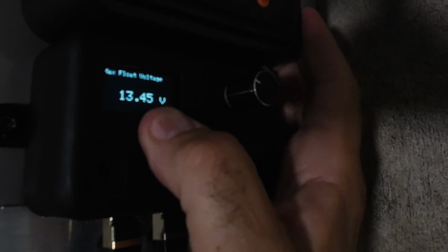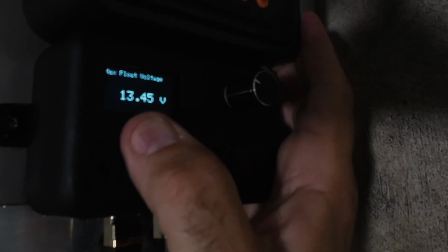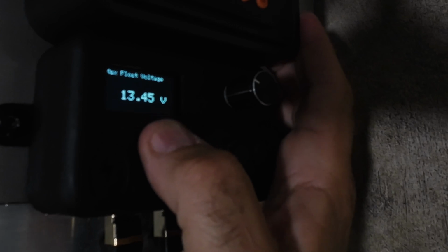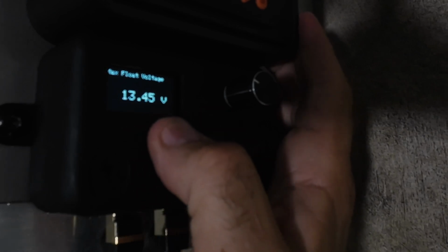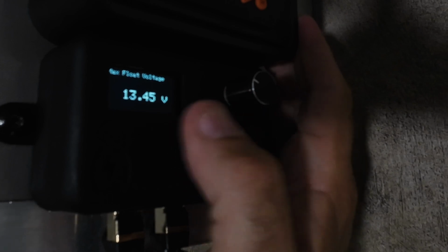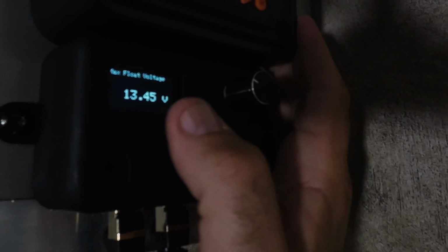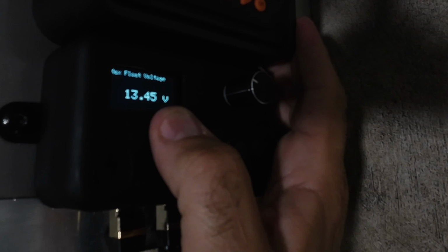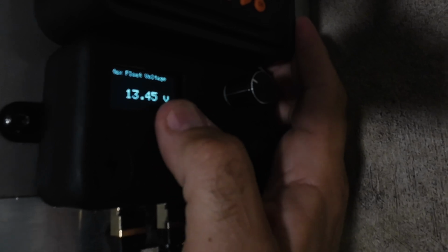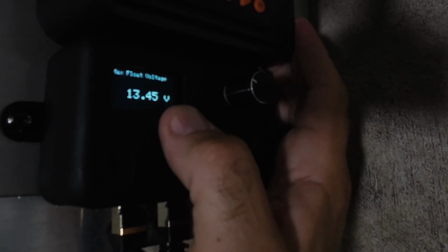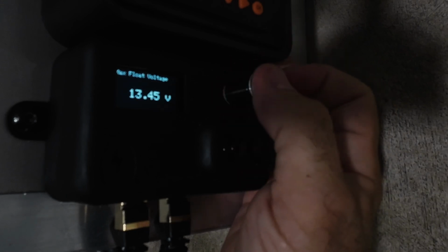Max float voltage. Oops. This is technically the voltage that I'm going to talk about chemically, is 13.48 volts. I set it for 13.5 by default. Above this line, low current overcharge can happen. The cathode can be damaged. Below this, everything seems to be safe. It's the activation energy of that chemical reaction. Technically, it'd be 1/4 of that per cell. You can adjust that number, but that's a good place to put it.